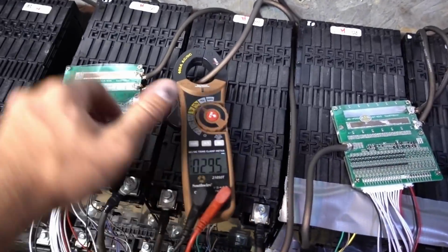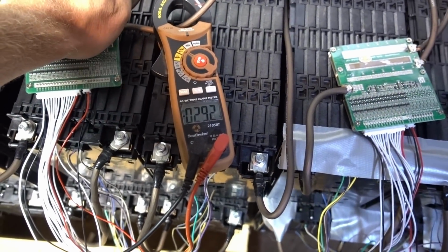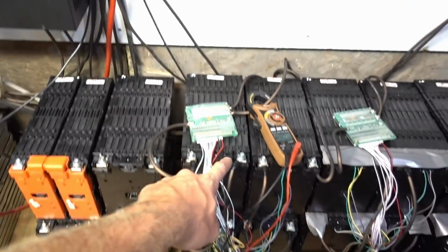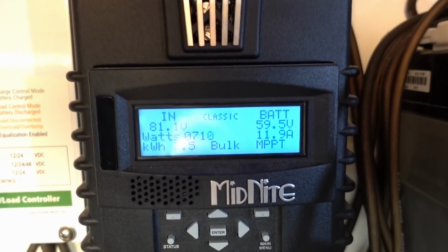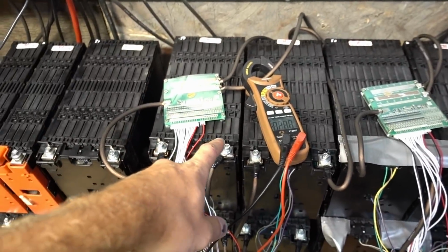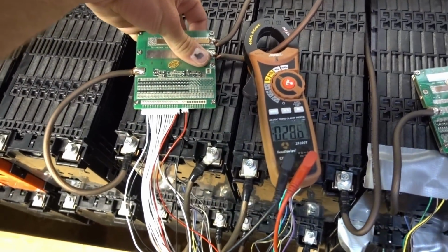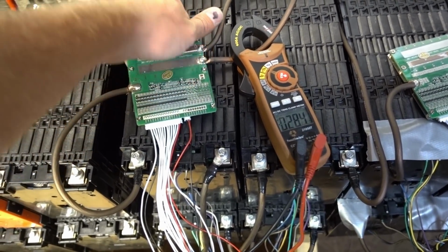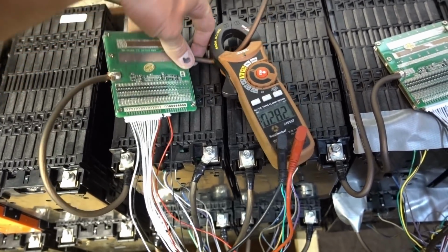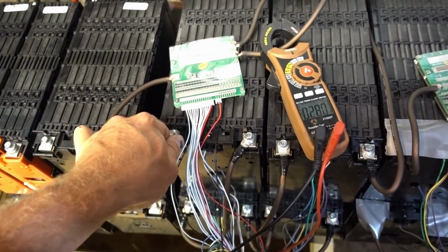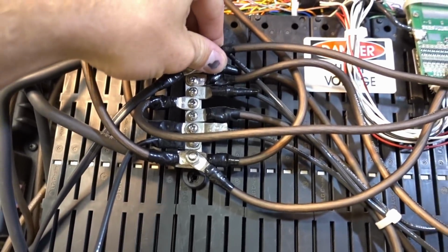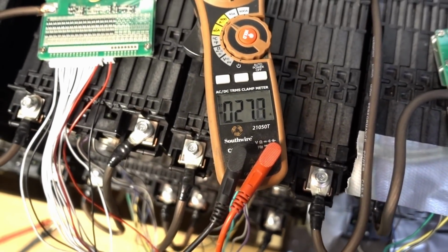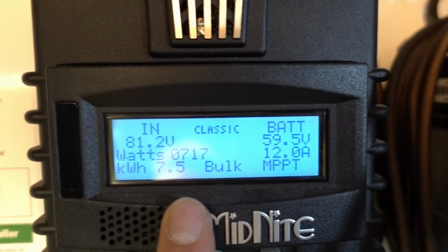So I just connected the BMS. We got 30 amps coming out of the BMS because we got a 2.7 volt difference between this pack and the rest of the battery bank. So we're charging the battery bank through solar, and we're discharging this battery into the rest of the bank, so this battery will go dead fairly quick. Just checking my BMS board - it's not warm, connections aren't warm, so it looks like it can handle 30 amps, that's good. Everything seems good, and you can see we're dropping in amperage because this battery is pumping into the rest of the bank and they're equalizing. Since I hooked it up, this has gone up 0.2 of a volt. That's also because the solar's charging it as well, but that's going to continue to go up and this will go down.